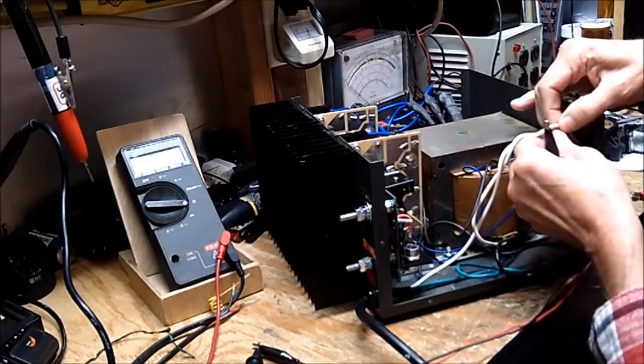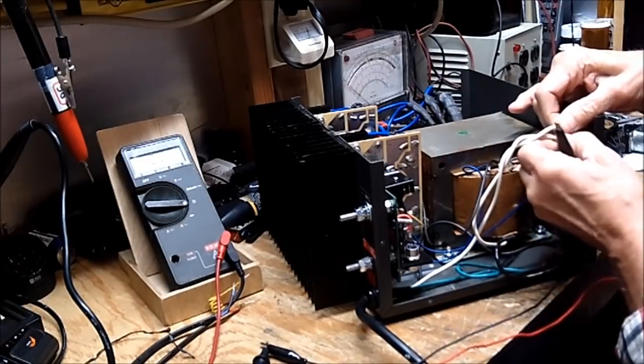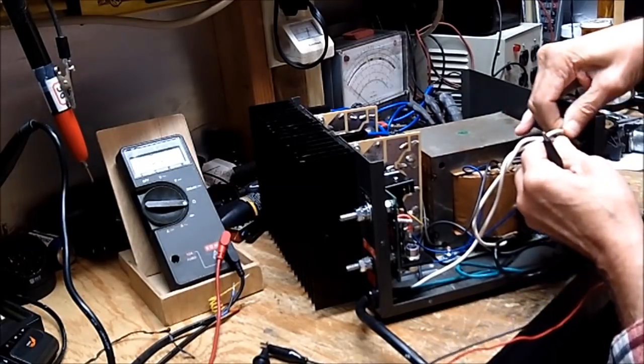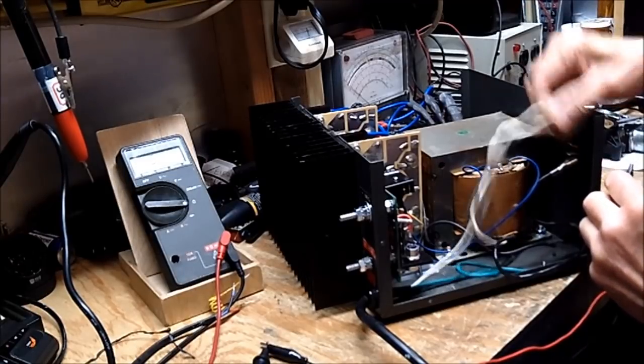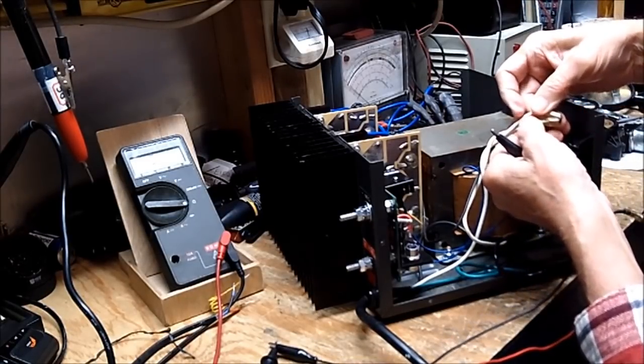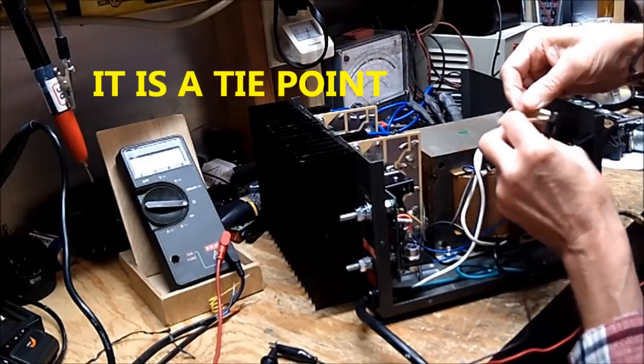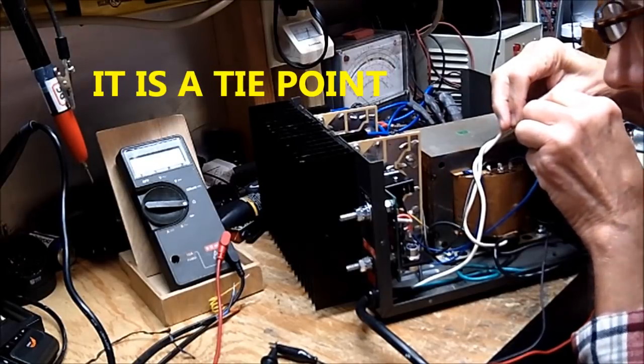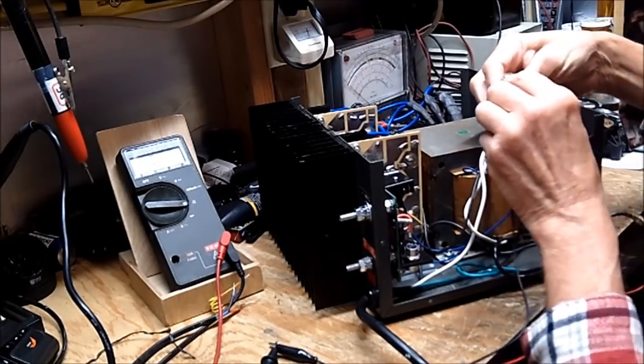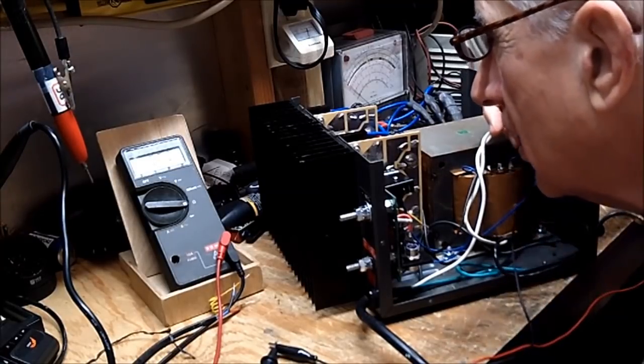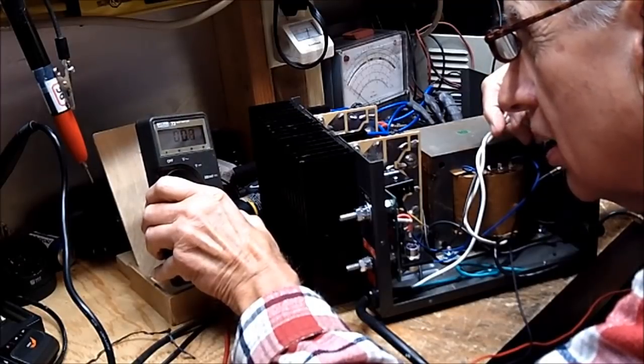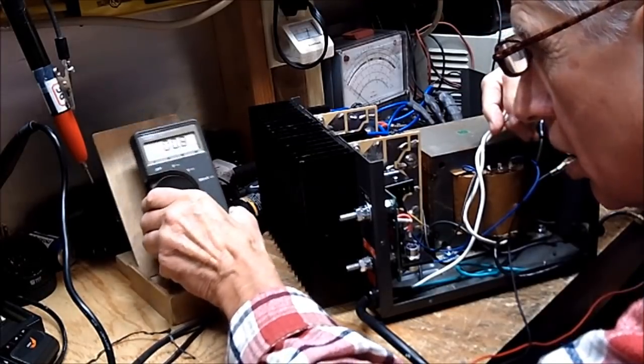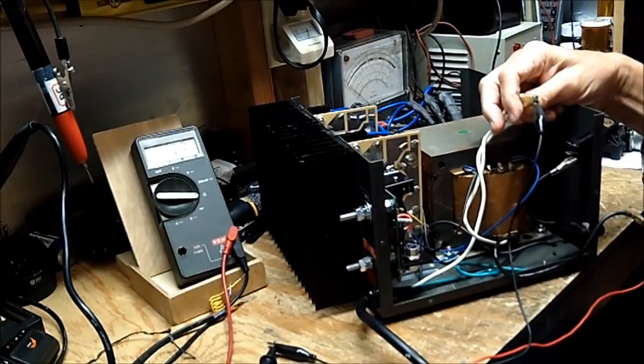So we want this second terminal from the top. It's not coming off, but this one is - oh, they both come off, they're both together, okay, alright, they're both fixed together. Let me see now... 0.8 ohms - that's awful low for a primary, that sounds like a secondary reading. But it's not open then, if I'm understanding this correctly.